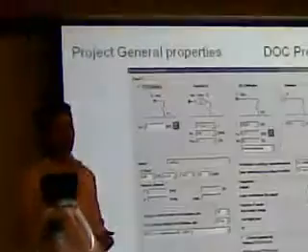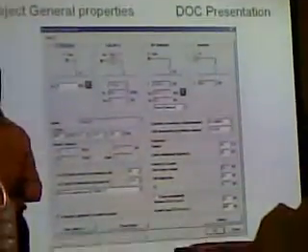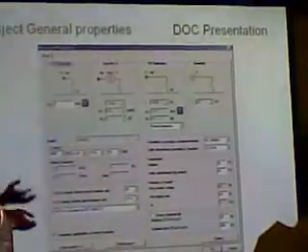Of course, we have to give the transformer rating, and then the impedance, which is important data for the transformer. Basically, the short circuit level changes based on the impedance level: the resistance, reactance and impedance.